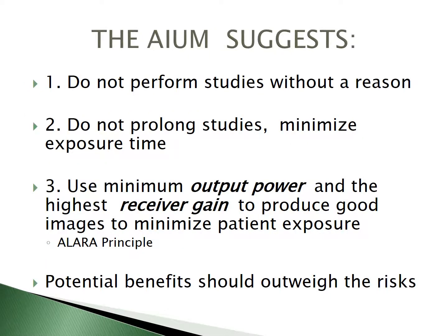To make sure that we are keeping a professional standard and not posing more risks to our patients, the AIUM suggests that we are not going to perform any studies without a reason, that we are not going to do prolonged studies and will minimize the exposure time, and that we are going to use the minimum output power and the highest receiver gain to produce good images. That goes back to the ALARA principle, as low as reasonably achievable. And whenever we are doing studies, we recognize that the potential benefits should always outweigh the risks.